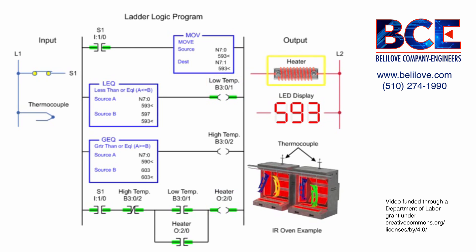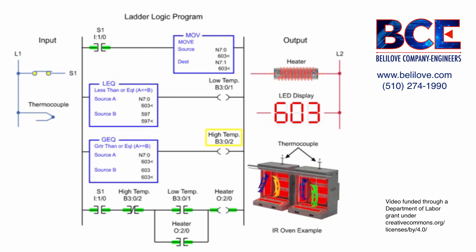The heater remains on as long as the low temp output is true and the high temp output is false. As the temperature rises above source B of the less than or equal to instruction, low temp turns off and heating continues. Reaching 603 degrees or more, the high temp output is enabled since source A is equal to source B of the greater than or equal to instruction.